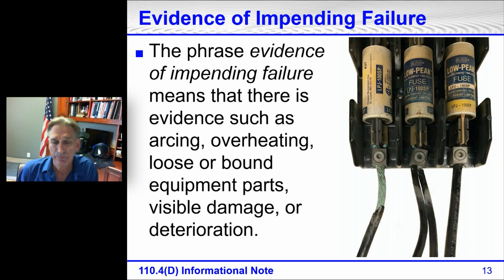Plus, the minimum size you can parallel is 1/0. That does not look like a 1/0. Also, all of the conductors would have to be paralleled the same. So anyway, this is absolutely evidence of impending failure. Someone asked in a class, well, how do you know this is in there? Well, you don't until you open the piece of equipment up, like a disconnect or an industrial control panel. Once you know that it's there, though, that equipment is in abnormal operation. What that means is, in order to turn this equipment on or off, even with the door closed, you have to be suited up, wearing arc flash PPE just to turn it on or off, if you know that there is evidence of impending failure.